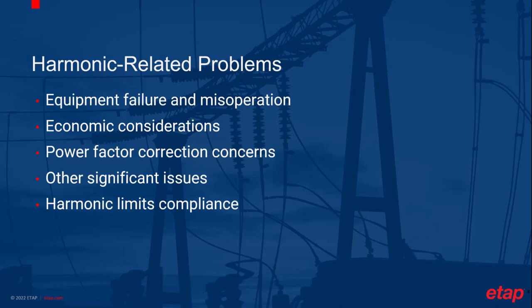And there have to be economic considerations evaluated with regard to harmonics, such as the losses of motors, the losses of cables and transformers, device sizing, and the utility imposed penalties. When you do power factor correction studies, the capacitors require special considerations with regard to harmonics as well. And there are other significant issues, such as the interference to communication systems by higher frequency electromagnetic field. All the above states why harmonic analysis is important.